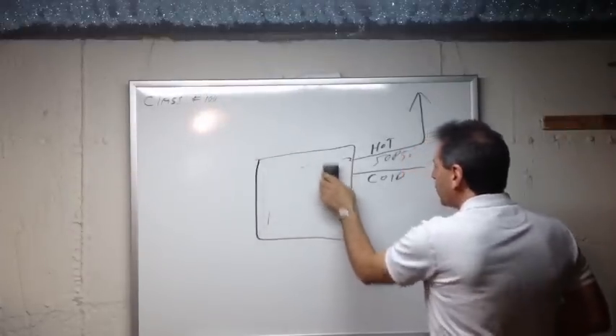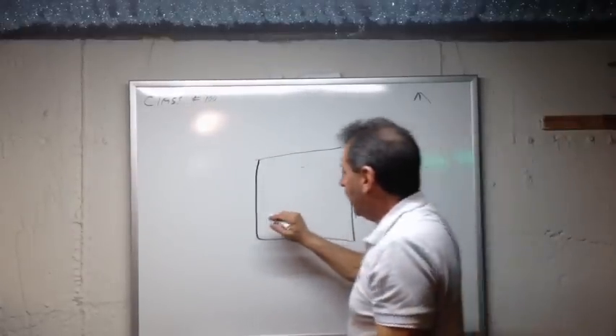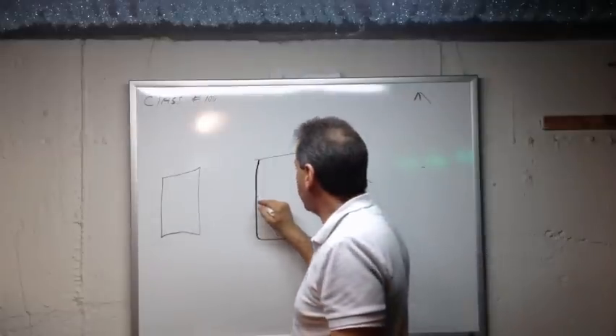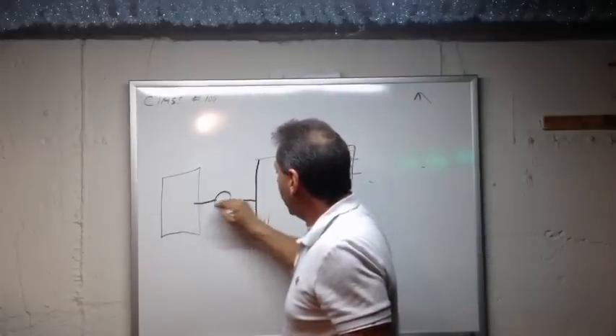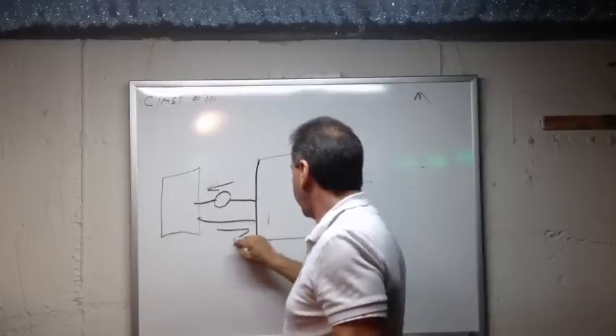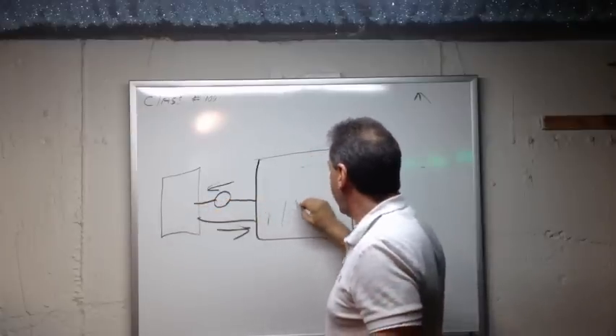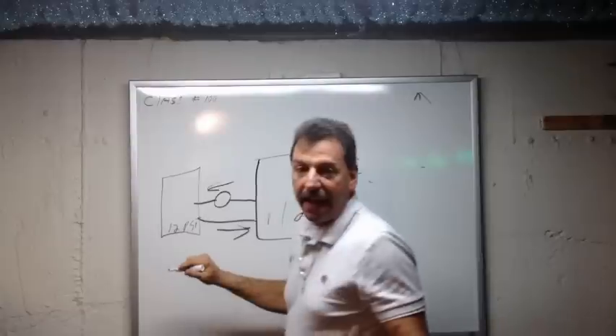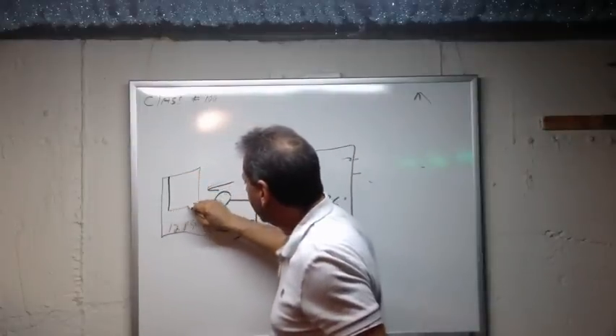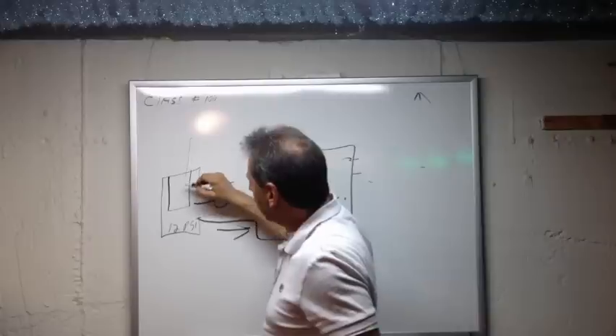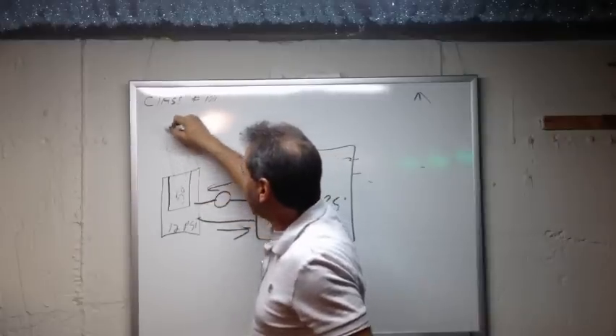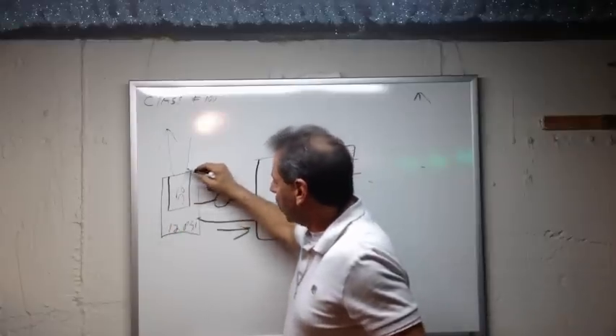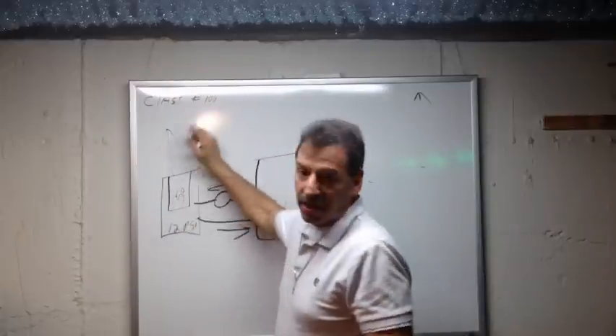The other scenario is besides these coils, you have your boiler, and you have a storage tank standing up next to your boiler. There's no fire in the storage tank because the plumber stole the hot water from the boiler with a circulating pump. And that feeds into the storage tank and back to the boiler again with the flow being this way. It goes in and comes back. This is all 12 PSI in here and in the bottom of this tank. But this tank also has another tank inside it, which cold domestic water goes in at 50 PSI, and hot goes out to your shower.